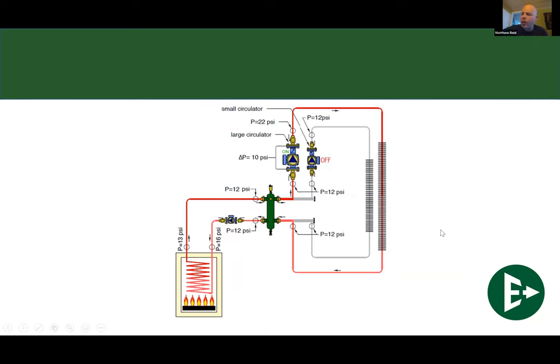A very good friend of mine always used to say, when it comes to hydronics, it depends. What's wrong? How much does it take? What size do I need for this? Well, it depends, because everything depends on everything else in the hydronic system. But with a hydro separator, we're changing that. We're setting that on its head. Now it's just, this is the way we do it, because that is the most effective way to protect that boiler.